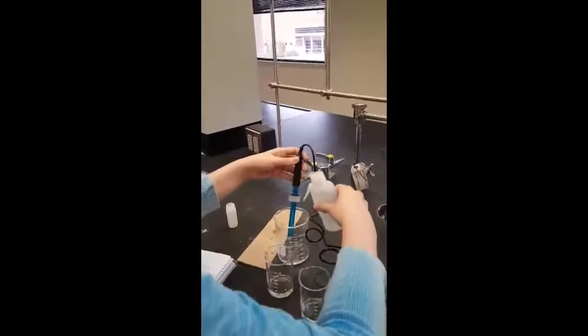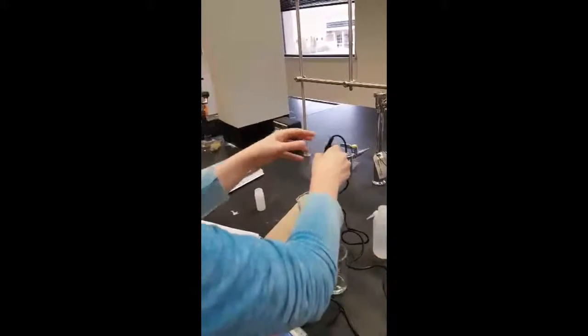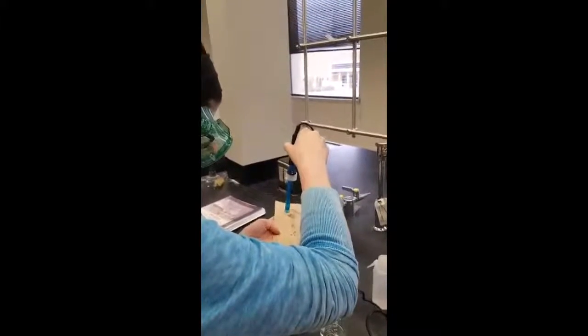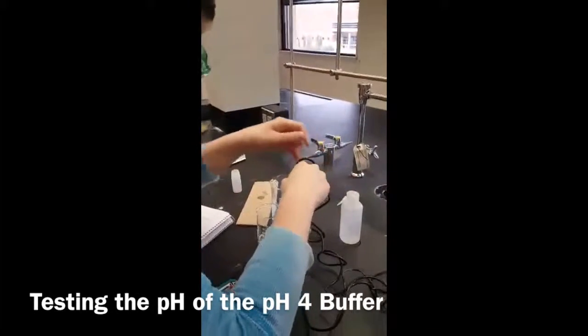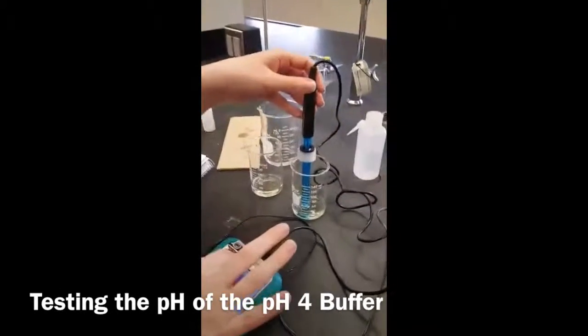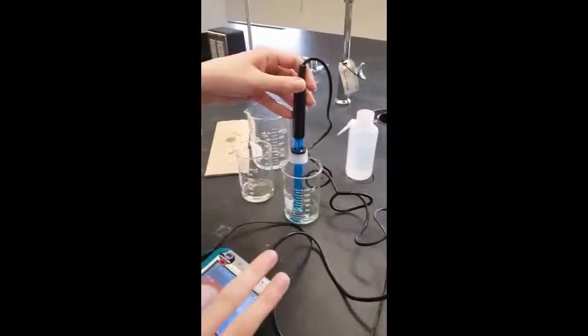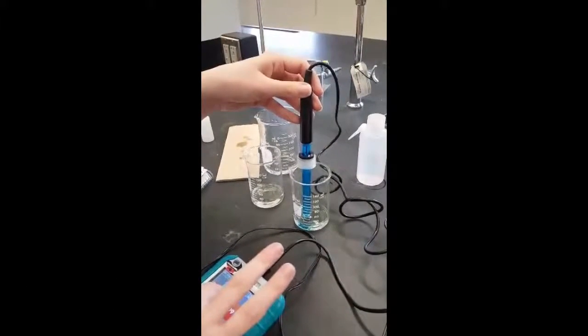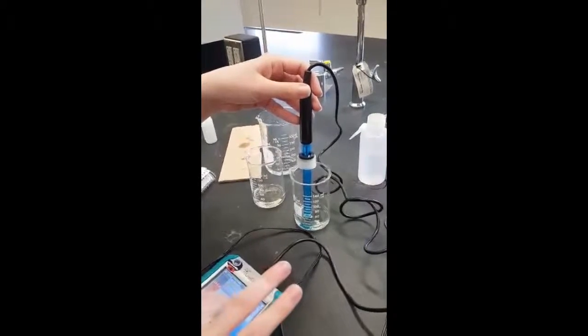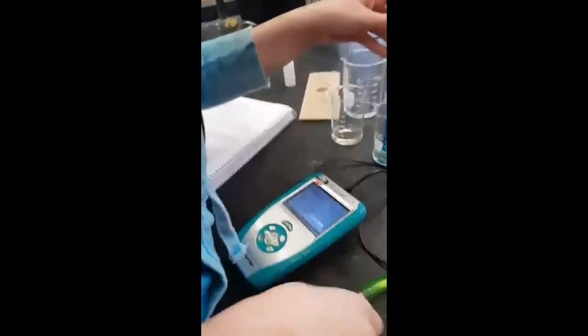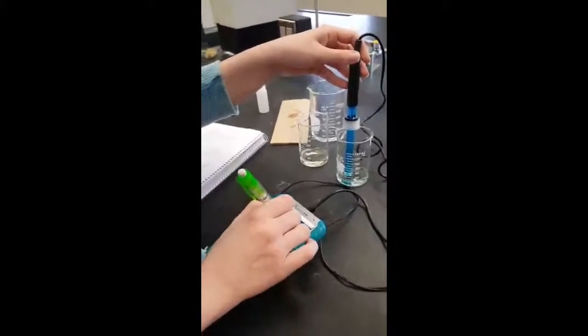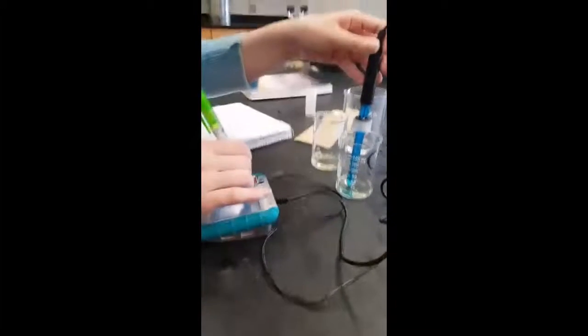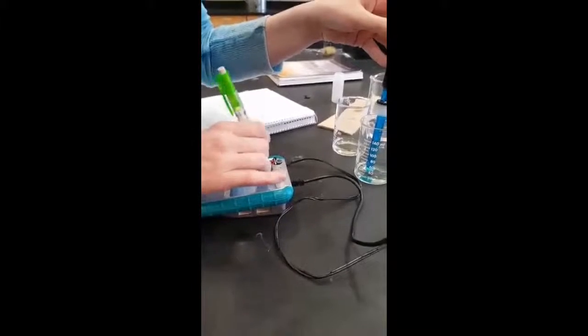Then on my screen, I pressed Sensor, then Calibrate, then I pressed where my pH sensor was located. Then I pressed Calibrate Now. In the first box, I put 7.0 since that was the pH of the buffer solution, and pressed Keep. Then I rinsed the probe with distilled water over the waste beaker again, patted it dry, then placed the probe in the solution with a pH of 4, which is yellow.